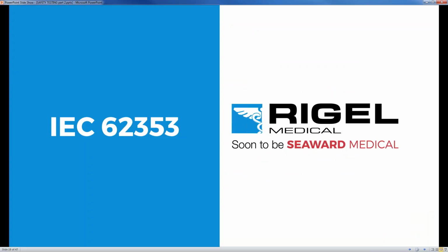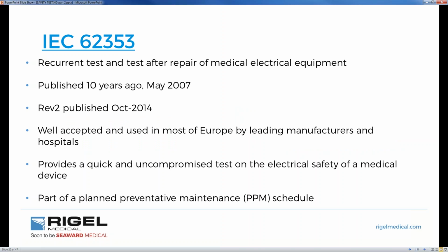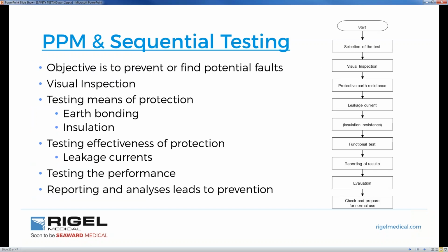That was 60601. Now we're going to talk briefly about 62353. 62353 is recurrent test and test after repair of a medical device. Published 10 years ago, or 11 years ago now. The second revision came out in October 2014, and it's well accepted and used in most of Europe by leading manufacturers and hospitals, but it's been adopted in other areas of the world too. It provides a quick and uncompromised test on electrical safety of medical devices, part of the planned preventative maintenance schedule.